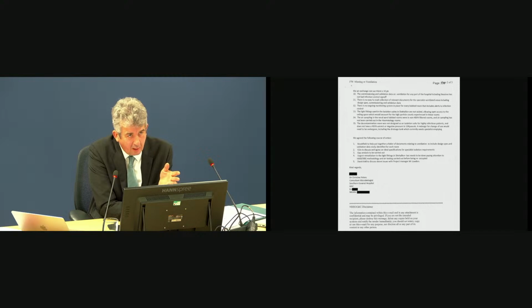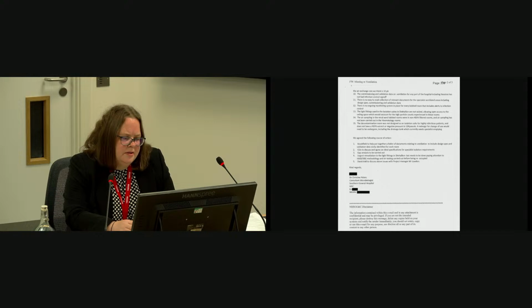The one that's missing is discussion of air change rates outside the isolation rooms. Why is that not in that meeting? Why are you not discussing air change rates outside isolation rooms at that point? I think this is a problem with interpretation of guidance in the SHTM 03-01 and the reference to neutropenic ward. I think most people at the time were taking that to mean neutropenic rooms.